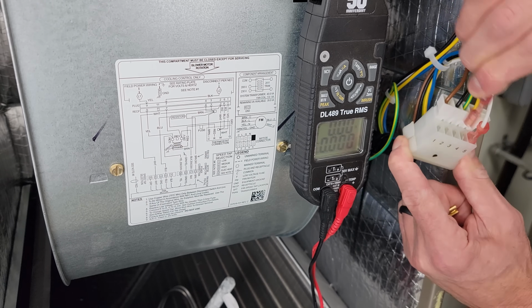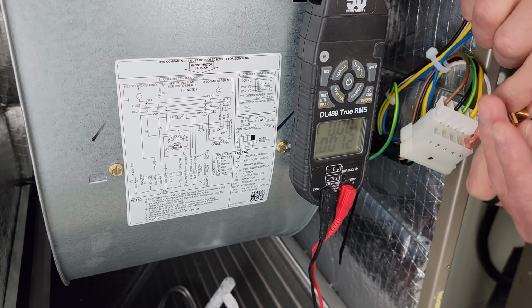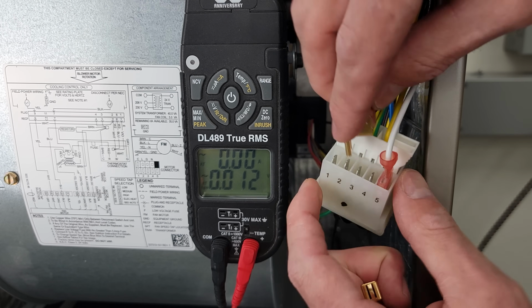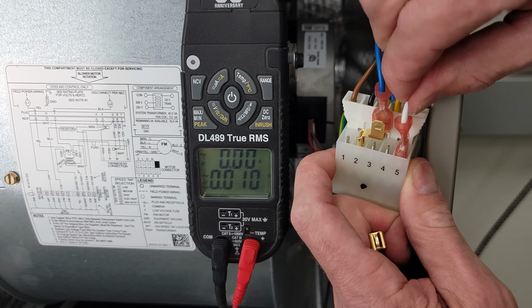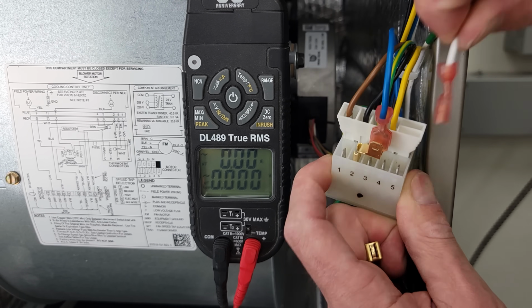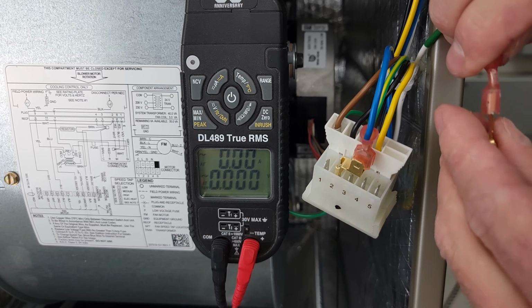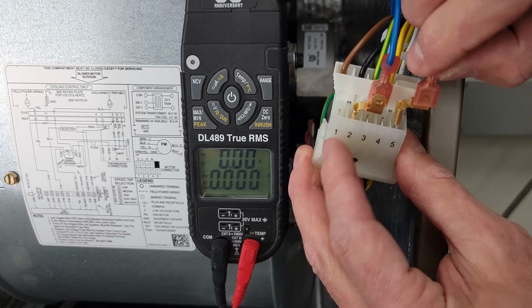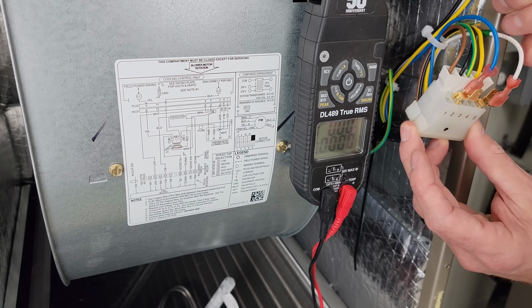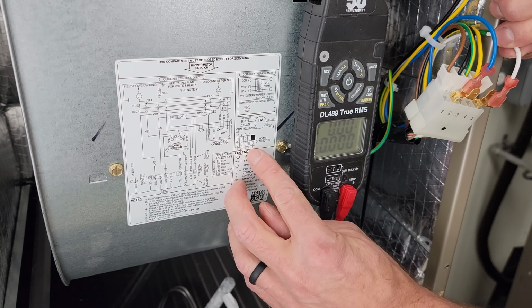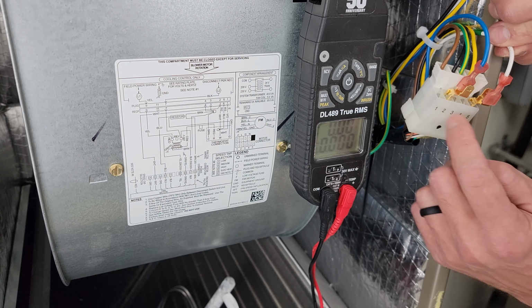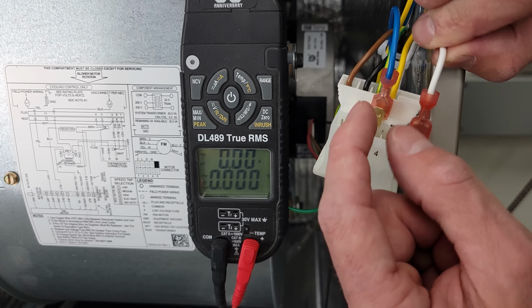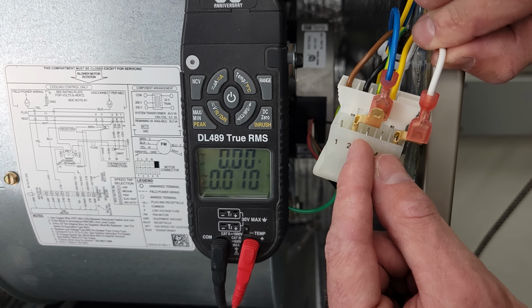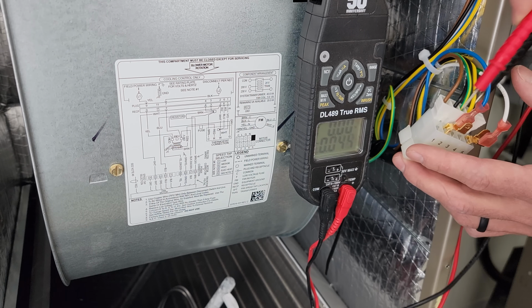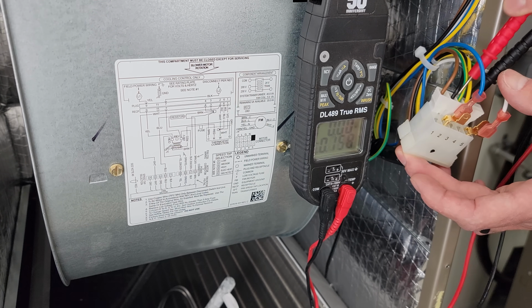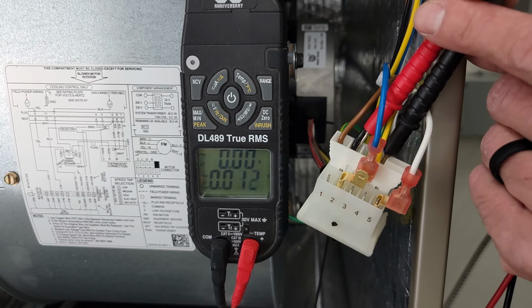We're going to go ahead and disconnect this just in order to add a adapter. Basically, you're just adding something in order to get at the terminal to take your measurements. And so the whole point of this is that these 1 through 5 are all 24 volt speed connectors. And so right over here you can see 1, 2, 3, 4, 5. Now the manufacturer may or may not program these, but as you can see, we already had these in there from the manufacturer on those specified speeds. Now we're going to take our probes right here and we're going to put them back into our high voltage power wires. Let's turn the power back onto this air handler.